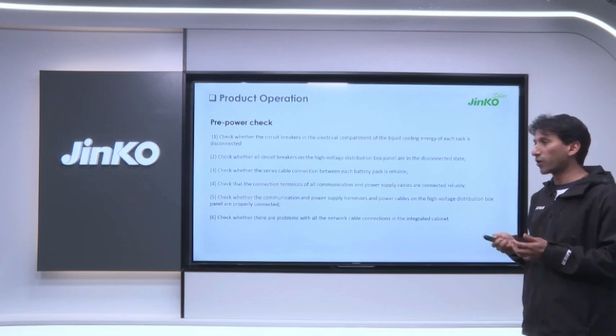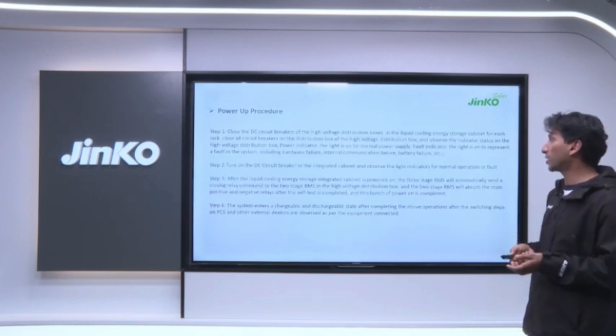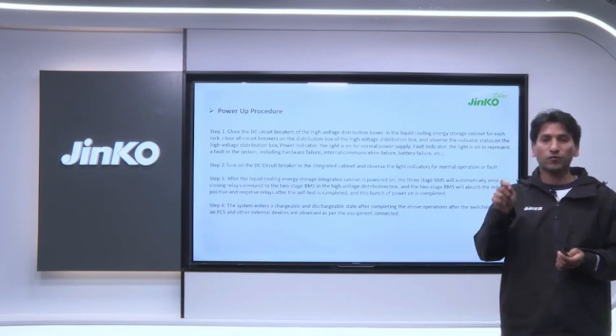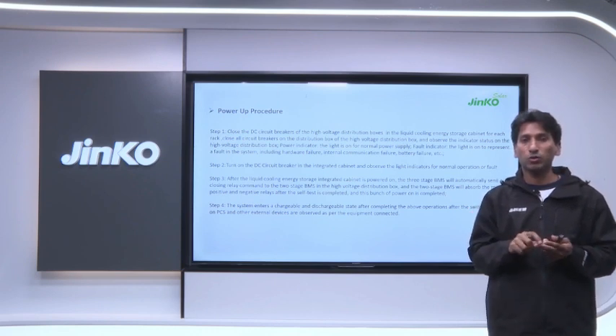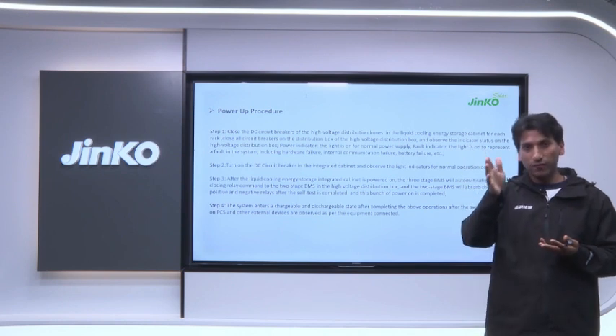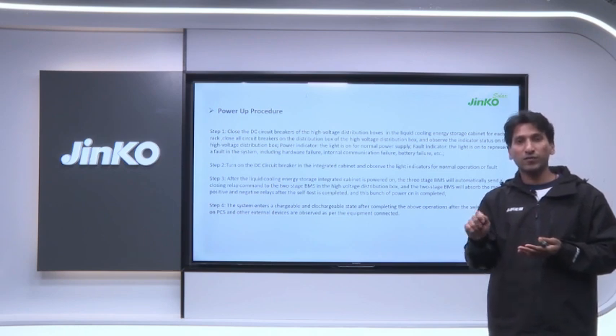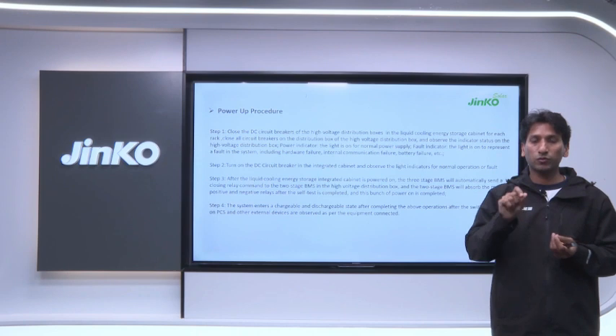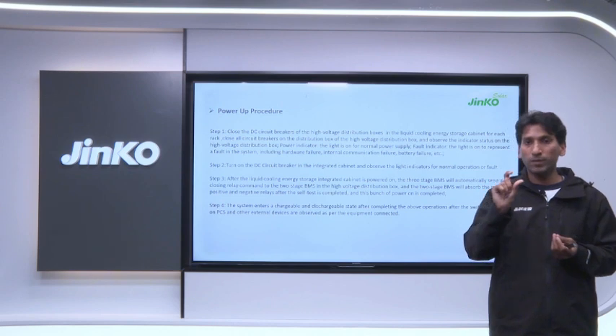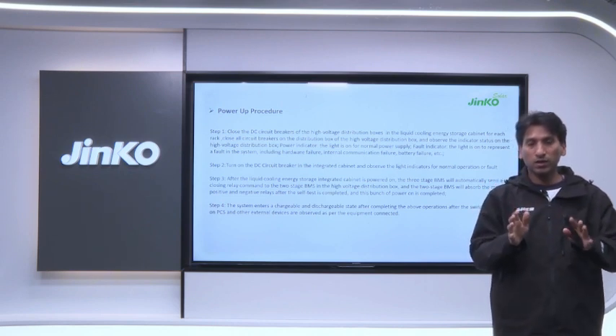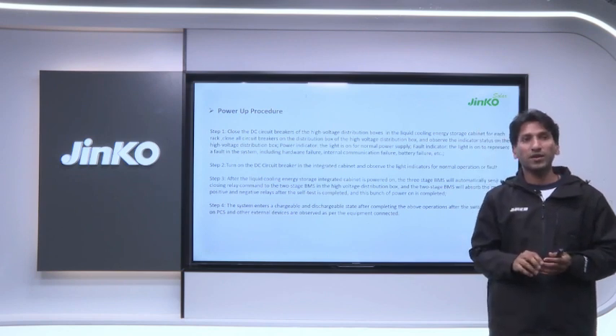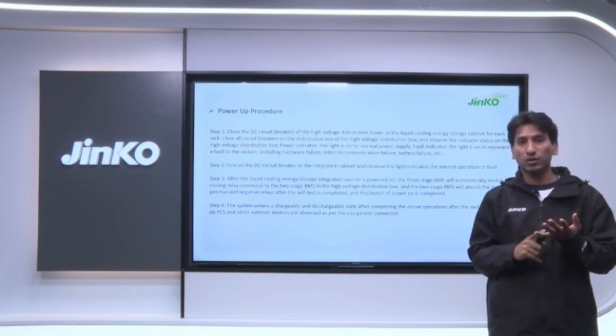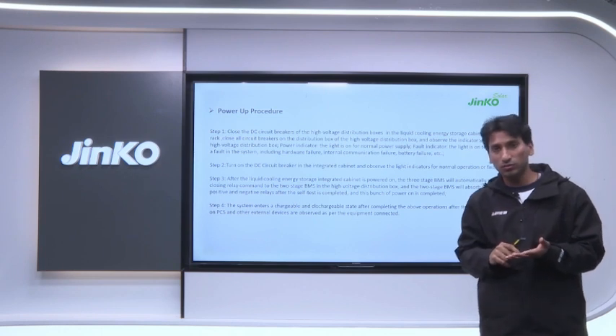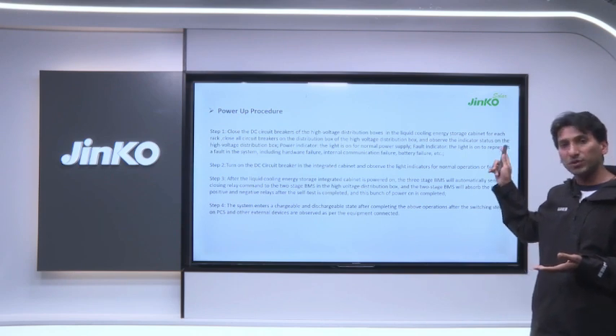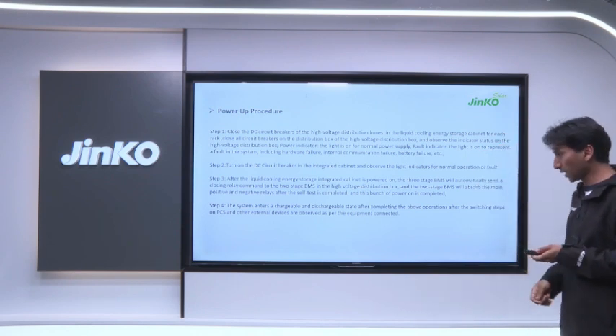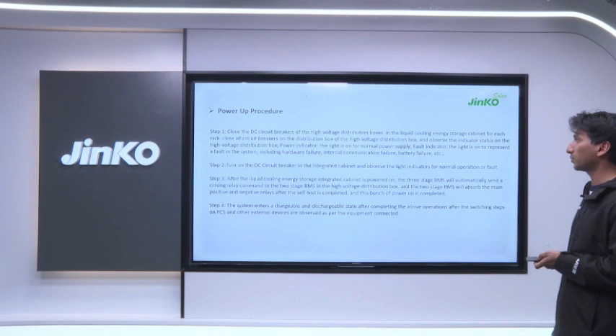And then when we go to power up the system, this is the way that we start. First of all, we close all the circuit breakers, all the DC disconnectors in each high voltage box in each rack. After we close them, we have to go to the integrated cabinet and close all the circuit breakers, all the MCBs in the integrated cabinet. After we have done all this, there are indications on the cabinet if it is normal or there is a fault. You can see there, if it is normal, the green light is on. Then we can move to the next part, go to the PCS side, the inverter side, and we power up the system from there. And this way the whole system can be powered up.